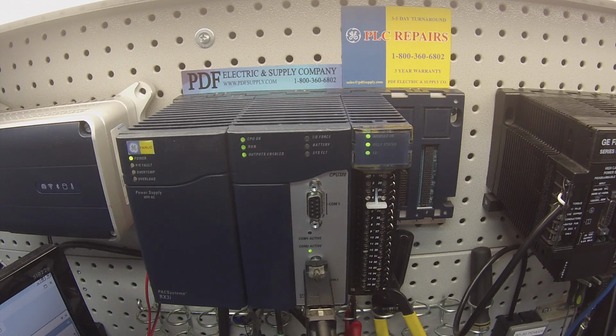It's a very sophisticated analog input card. So it should give you an exact reading. It shouldn't be fluttering around or anything like that, the values. If you have any of those problems, if any of those things fail or go wrong or don't go the way that this test was explained to you, then that's definitely a card that you know by testing now is broken. It needs repair or replacement.